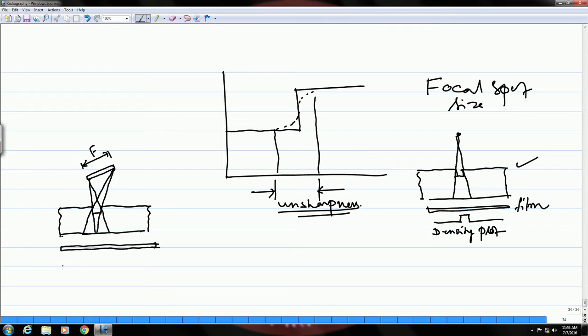this sharp boundary will appear as a diffused one like this. So, you will not see that sharp change which is there in the boundary, rather it will appear as a gradual change like what we have seen in this case also. So, this is due to the size of the X-ray source or the focal spot size. Okay. And this particular phenomena is known as unsharpness. And since it is related to the geometry of the source, it can be defined by a geometric parameter. So, if you simply take the ray diagrams now, you would be able to get an expression for this.